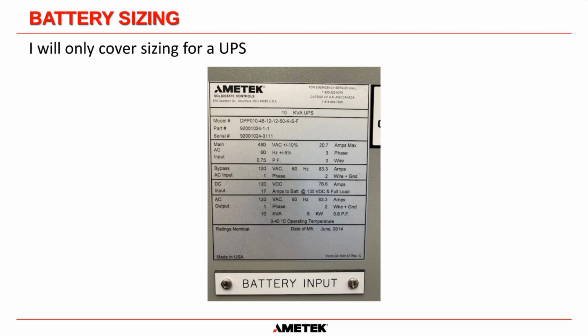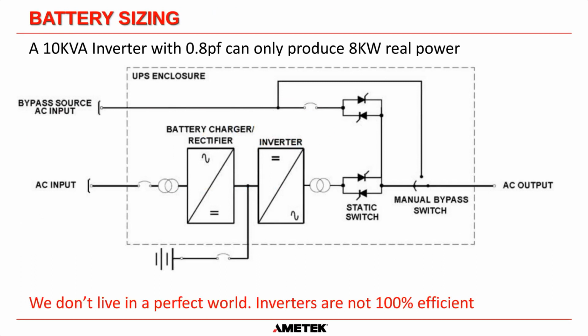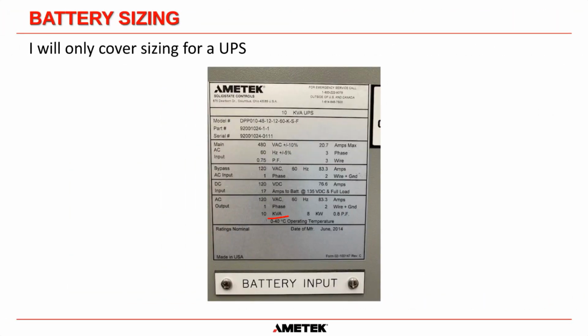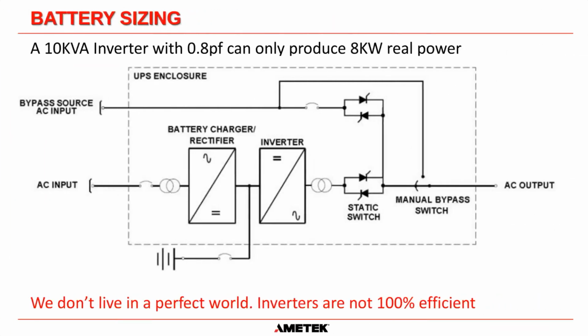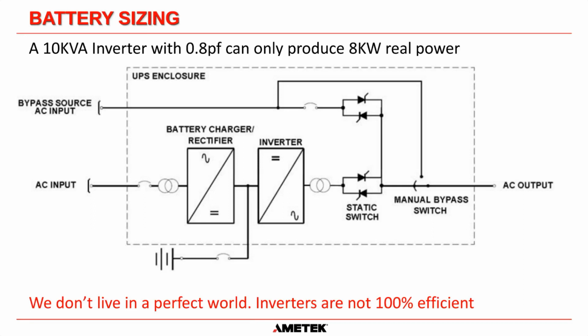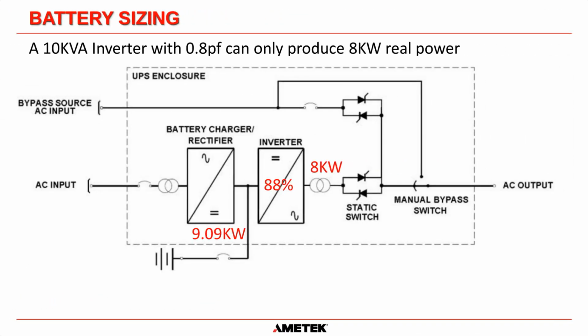So this is the rating plate for one of our 10 kVA DPPs. Okay, and it's saying that the DC input is 120 volts DC, so we know it's a 60 cell system. So we don't live in a perfect world. Inverters are not 100% efficient, and also a 10 kVA inverter has a 0.8 power factor. If we go back to the slide, you can see here it says it's a 10 kVA system, but it's a 0.8 power factor. So we can actually only put 8 kilowatts of real power out. So on the output of our inverter, we can only supply 8 kilowatts.